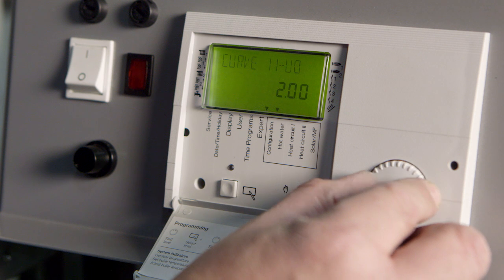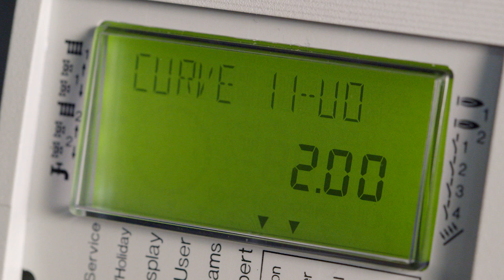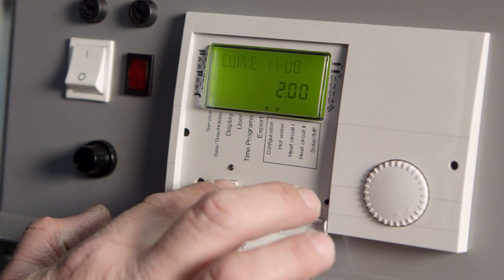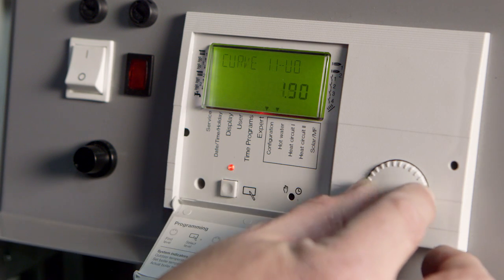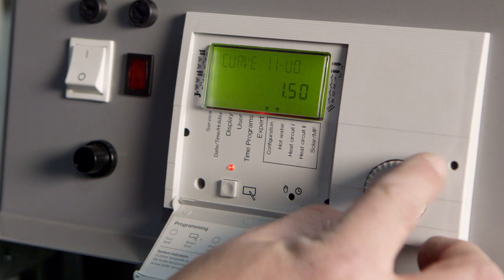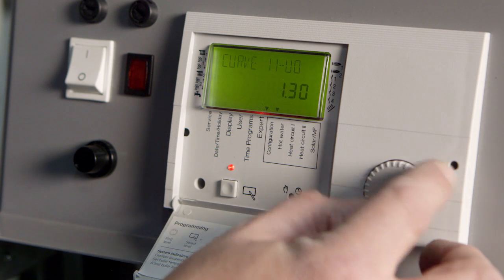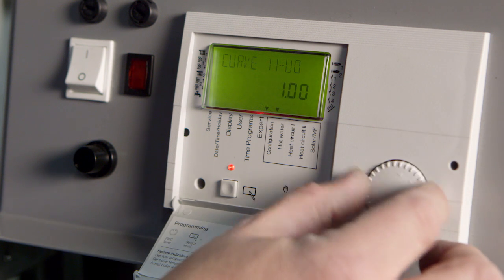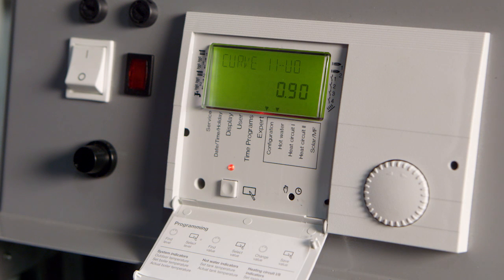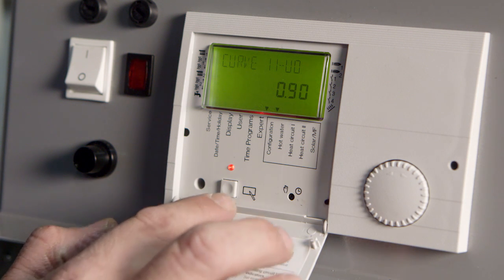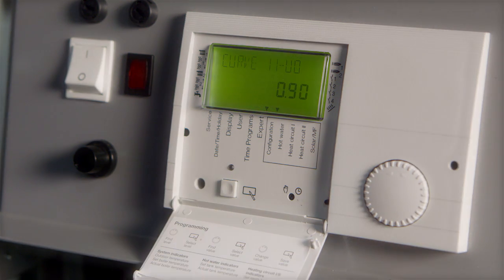Turn the rotary knob clockwise and scroll until curve 11-UO appears in the display screen. Press the program key. Use the rotary knob to adjust the UO voltage to below the voltage you set for U1. Once it's there, press the program key to store the setting. This now completes all of the required entries for operation in the 0 to 10 volt remote setpoint mode.